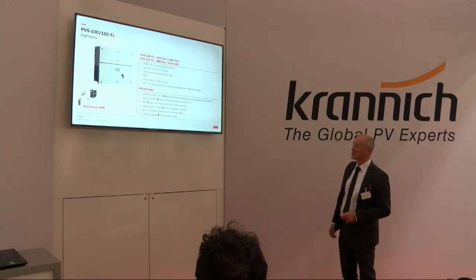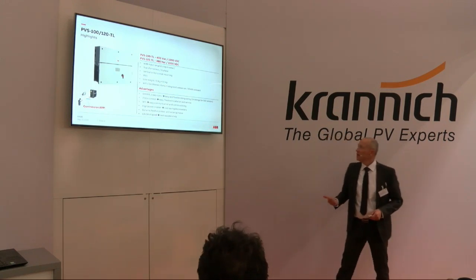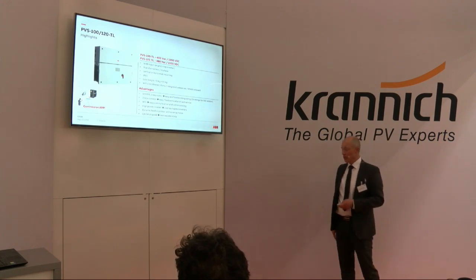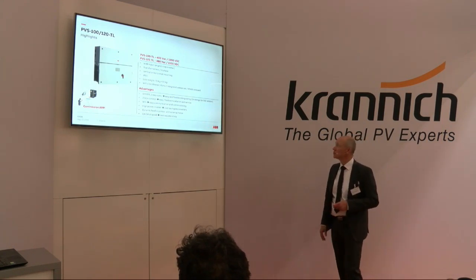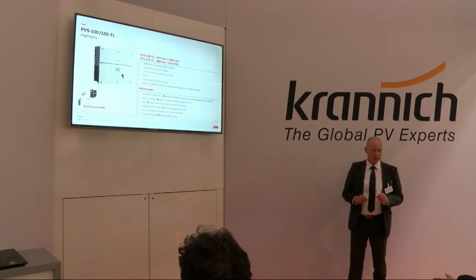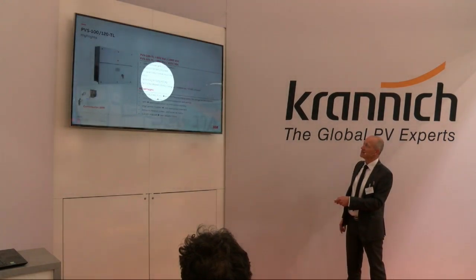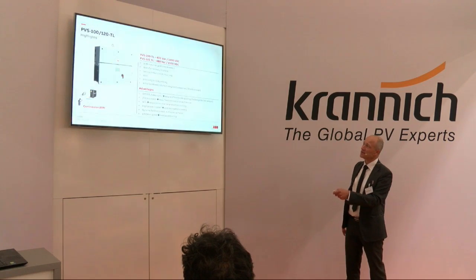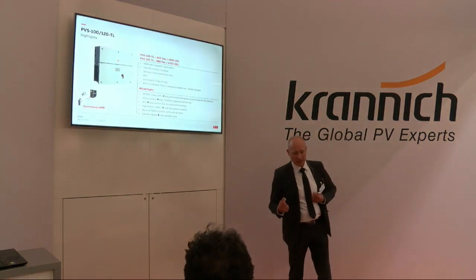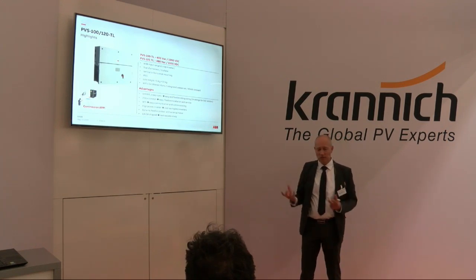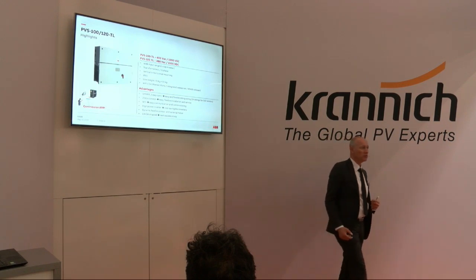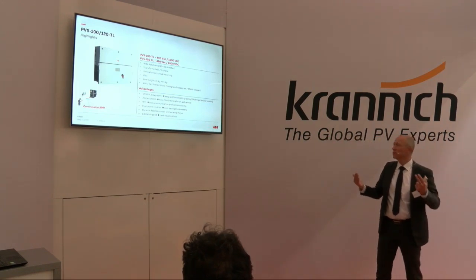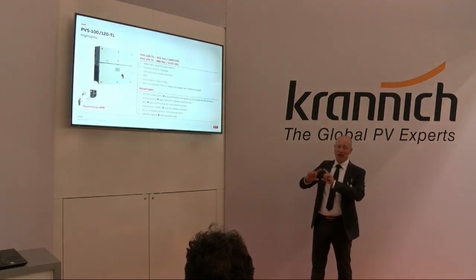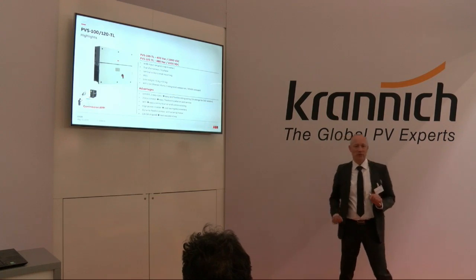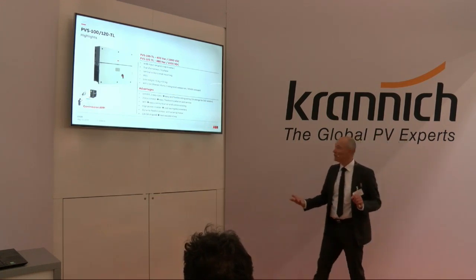Another topic is that we have 6 MPPTs in this inverter, each with 4 strings. So we have the possibility of connecting 24 strings for SX2. We have a 2-box concept. This is the reason why we split it down into 55 and 70 kilograms. In case of installation, you can start with the lower part, put all cables on, and finally put the power part on it. If you have a service case, you just have to remove the upper part and can exchange it without disconnecting any cables. It helps you to save time.